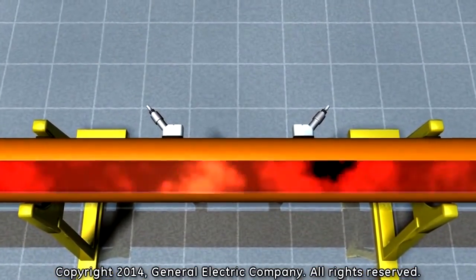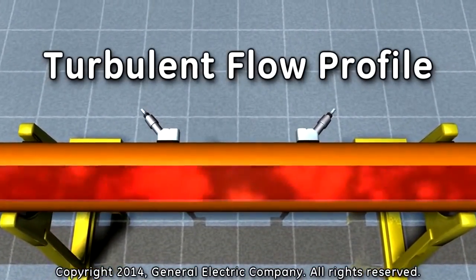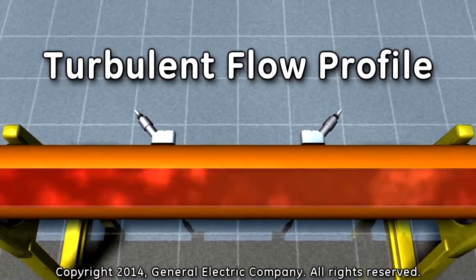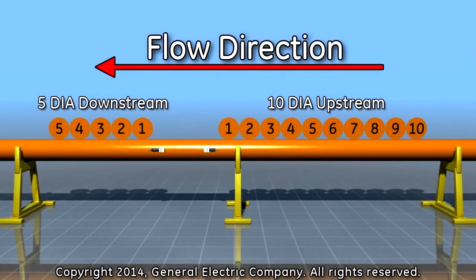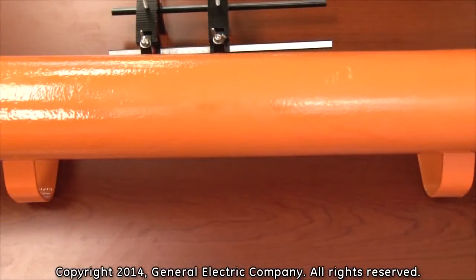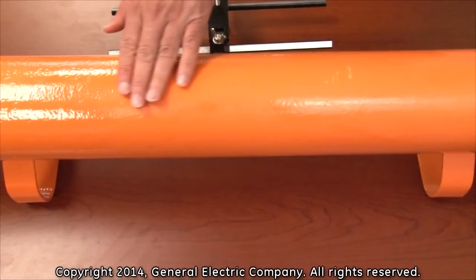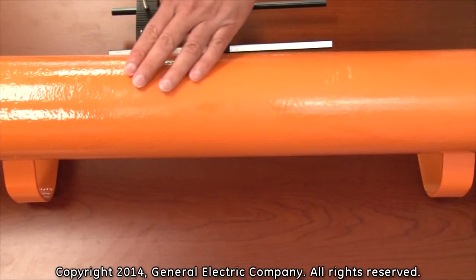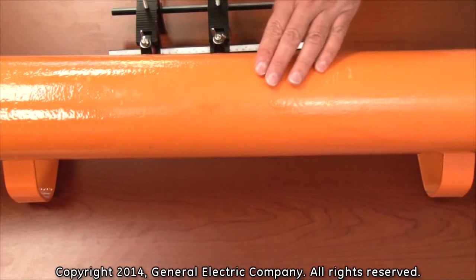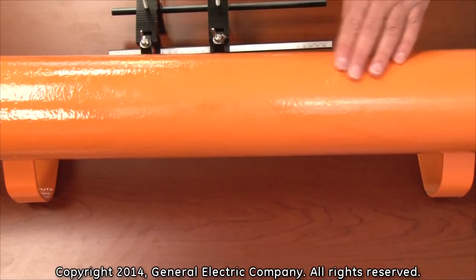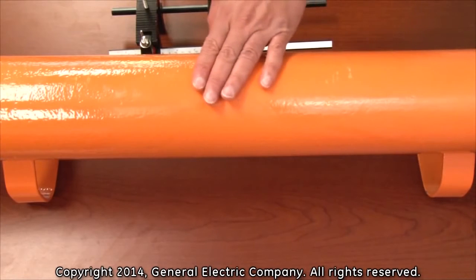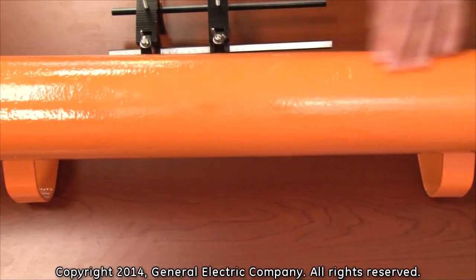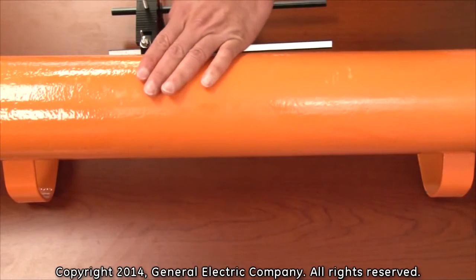In order to ensure the best accuracy for flow measurement, you must have a turbulent flow profile. You can achieve this by having at least 10 diameters upstream and 5 diameters downstream of straight run for the transducer locations. The location of the installation should be clean, flat, and free of any debris or buildup of corrosion or pits, etc. This is to ensure a good coupling of the transducers to the material of the pipe and provide for better sound propagation of the ultrasonic signal.